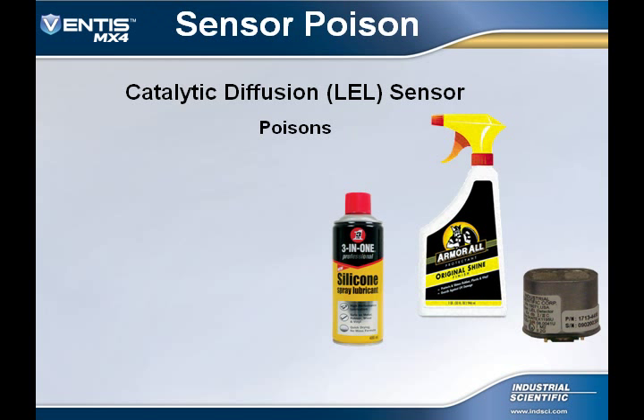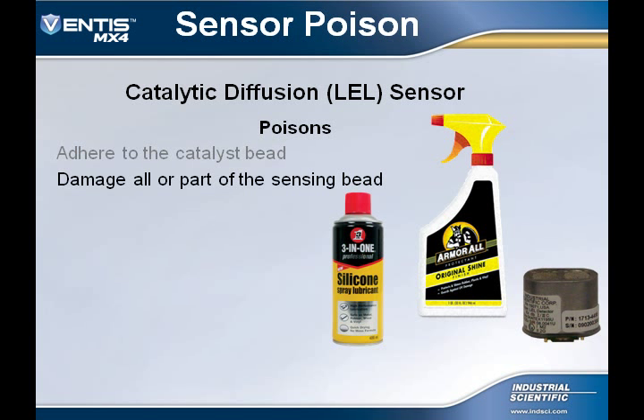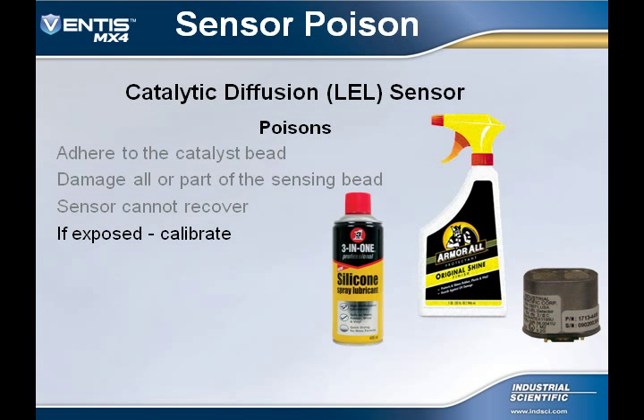One thing we need to be aware of with the LEL sensor is that there are some poisons that can affect its operation. Poisons will adhere to the catalyst bead. They will damage all or part of the sensing bead. The sensor will never recover if it is exposed to a poison. If you feel that the sensor has been exposed to a poison, a calibration should be accomplished to confirm its operation. If a sensor fails its calibration, then it will need to be replaced with a new one. A LEL sensor should last a good 3 years, but a poison will end its life instantly.